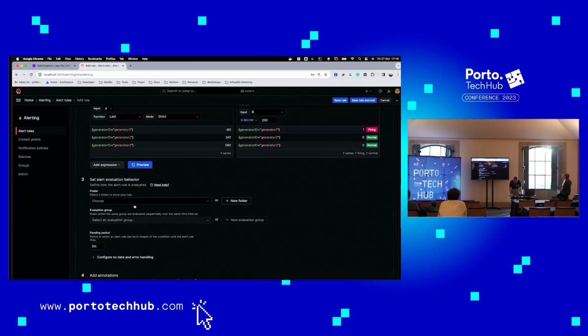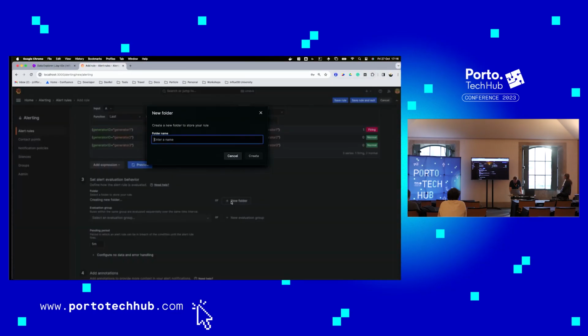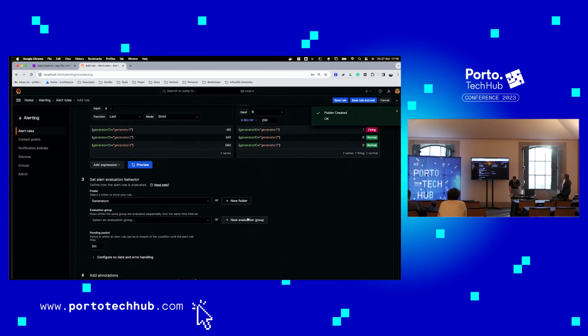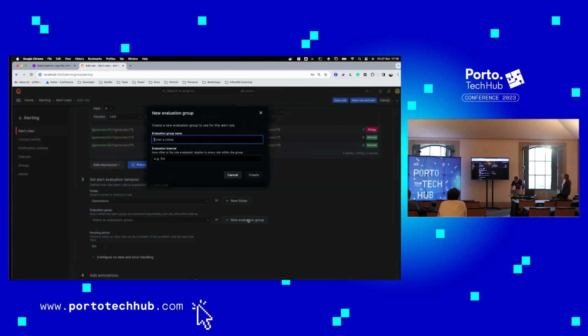I'm going to scroll down. What we can do is create a new folder for our alert. I'm just going to call this generators. Click create. We can then create a new evaluation group. I'm just going to call this fuel check. And then, just for purposes' sake here, I'm going to set a 10-second check on our interval just to make sure that we get an alert really quickly as part of this demo. So we're going to check our fuel every 10 seconds.